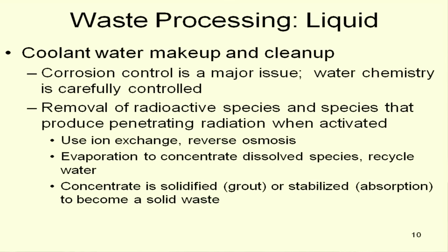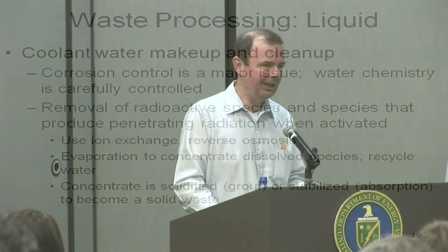And that means not only the pH and this kind of stuff, but inevitably, some of the rods are going to leak a little bit of something. You've got all these neutrons in the core. Some make activation products in metals, and the metals corrode, so they dissolve. So you get radioactivity moving around in your cooling water, and it gets in odd places in piping and pumps and can make maintenance a headache. So you try to keep the water fairly clean.